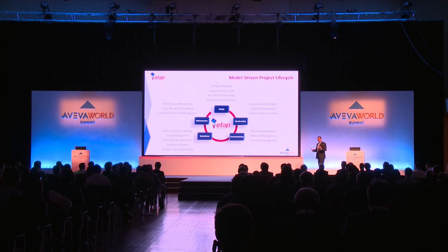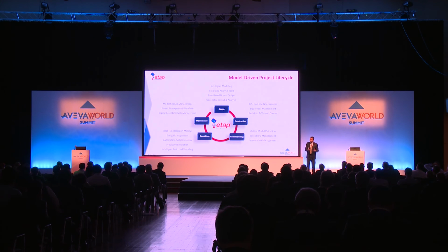Let's say you have a system online and you're planning to add a new process unit, a new section, a new phase to the project. You take a snapshot of the online model with all the validated parameters already online because it's operational, it has to be validated. You take that model, add your new section, go through the whole cycle again, back to operation. This enforces validation and having an exact as-built model.